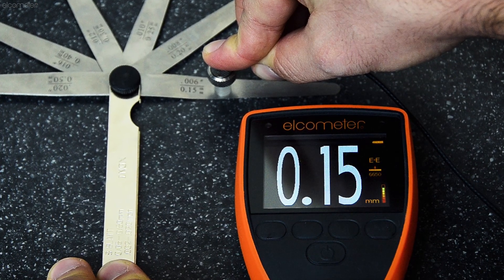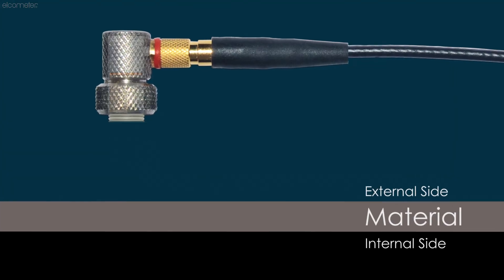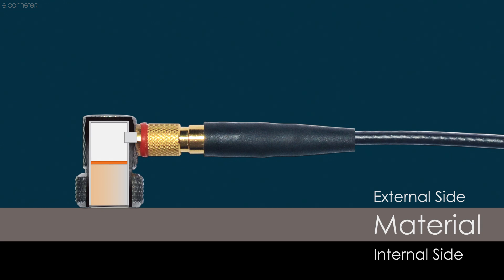So how does it work? Single element transducers consist of a crystal which emits an ultrasound pulse when triggered by a voltage. This energy pulse travels from the transducer into the material, aided by ultrasonic couplant, hits the back wall of the material, and echoes back towards the crystal where it's detected.